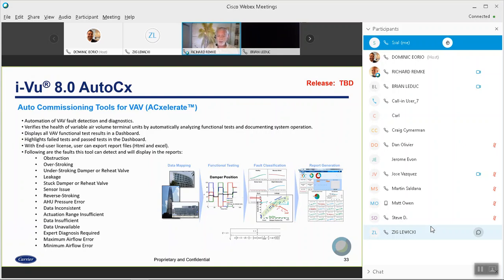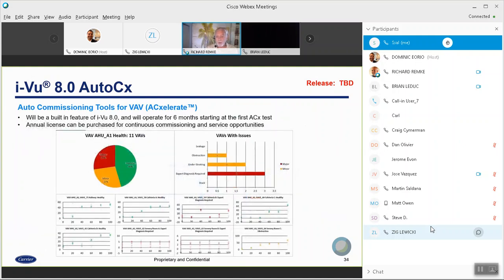And so for continuous commissioning, obviously, damper actuators don't always stay on the shaft. Reheat valves sometimes get stuck. Things happen. So you can certainly upsell your customers on providing this as a service to them, to give them these reports and good information. Here's just an example of how the reports can come out based on the system. Air handler 1 has 11 VAVs associated, and here are all the VAVs with issues. It tells you what those issues are.